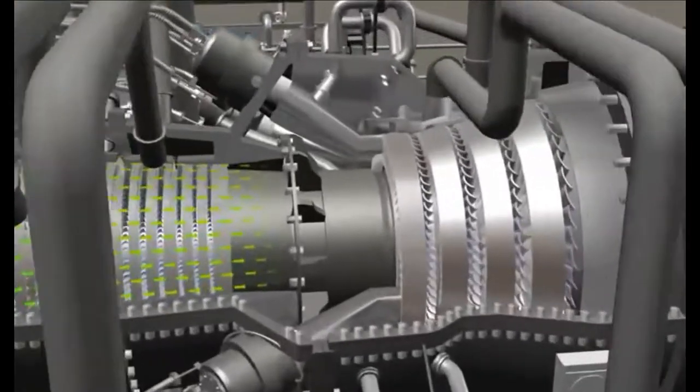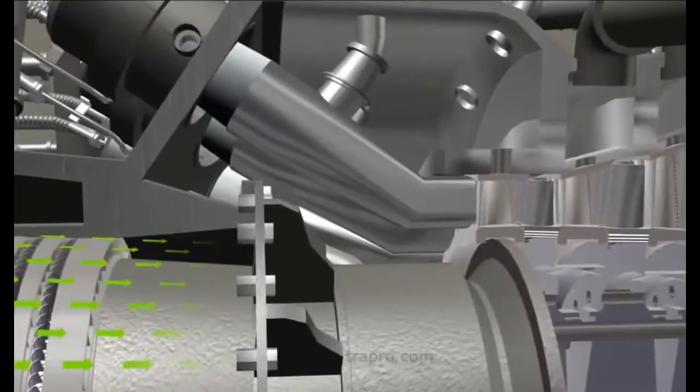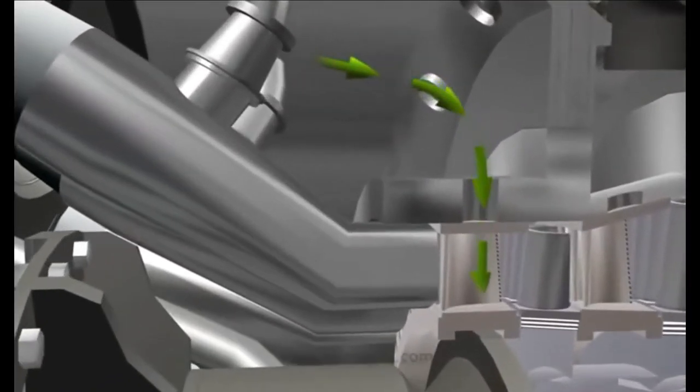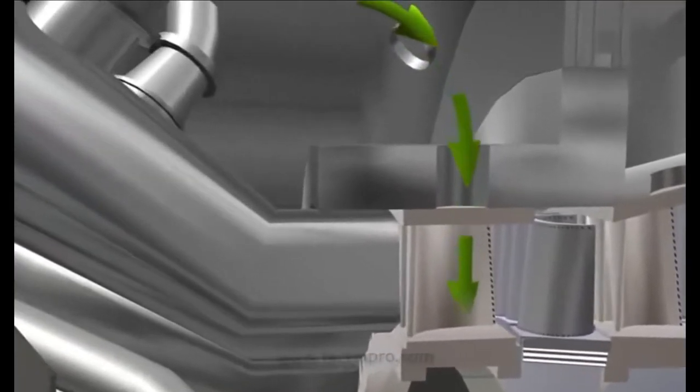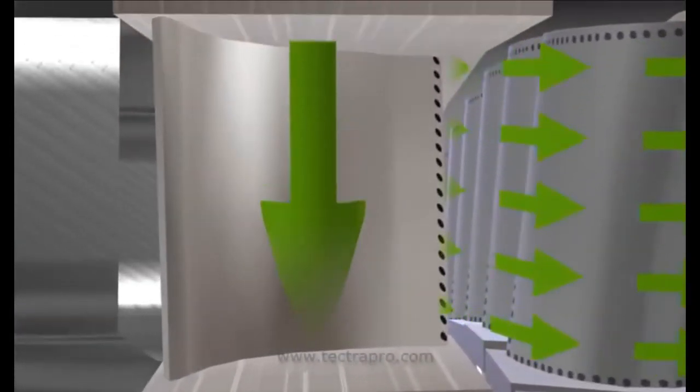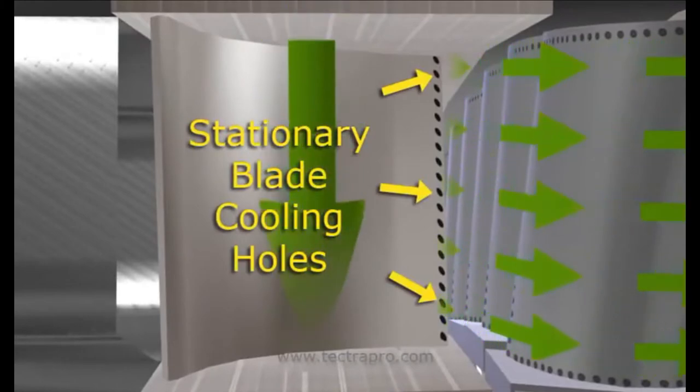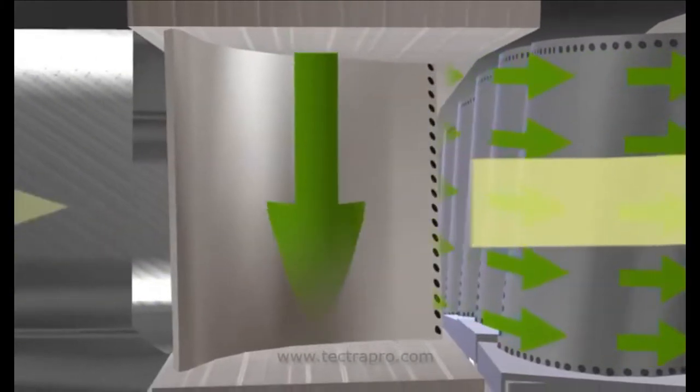The first row of stationary blades is cooled by air that is routed through the combustor shell from the compressor discharge. Cooling air flows through the hollow blades and exits the cooling holes on the trailing edges of the stationary blades.